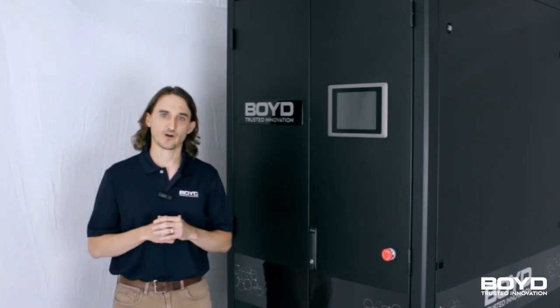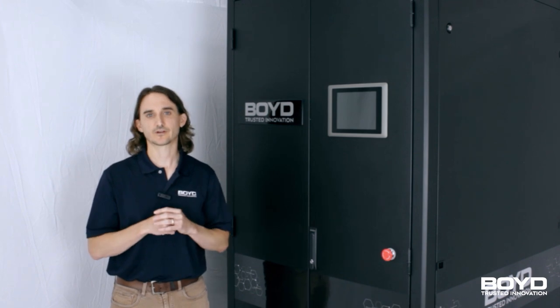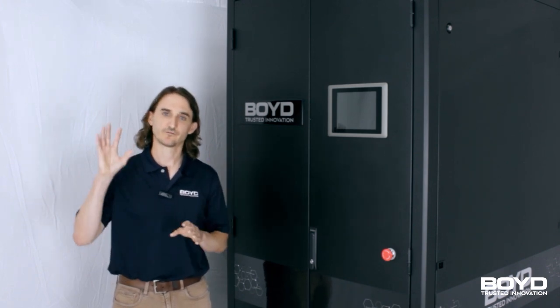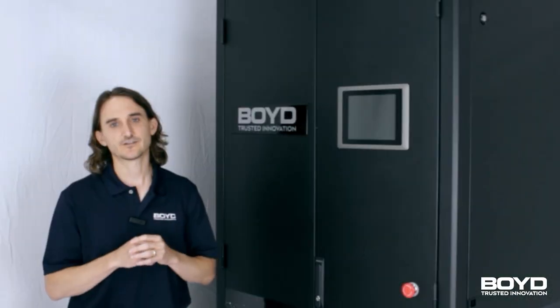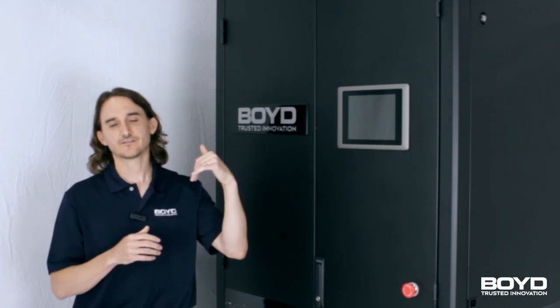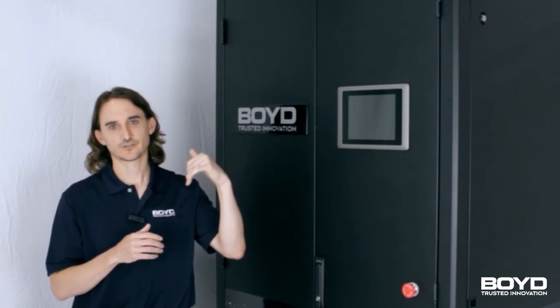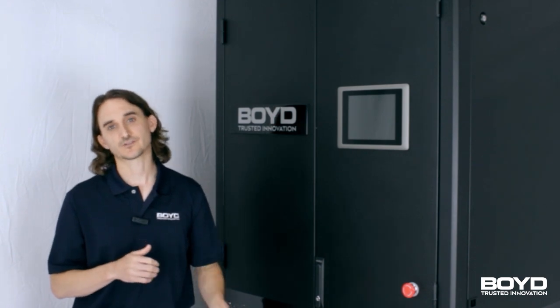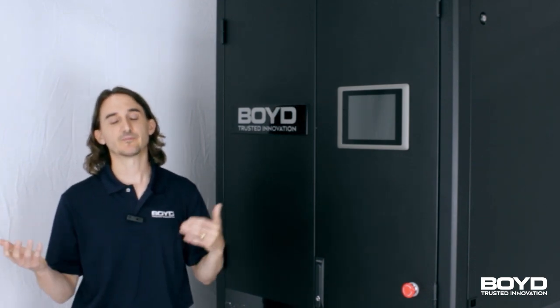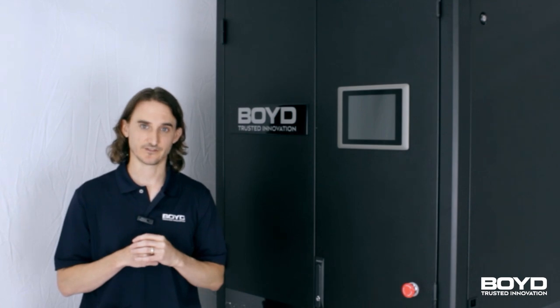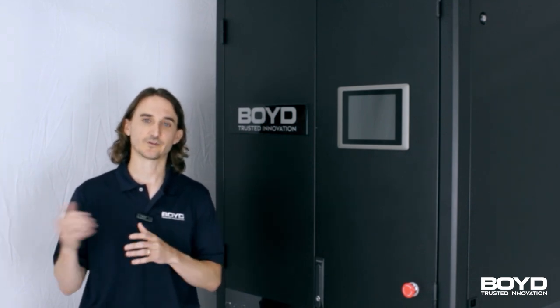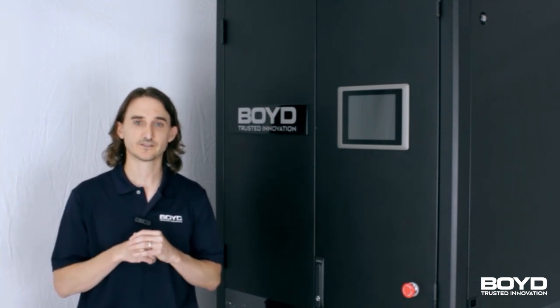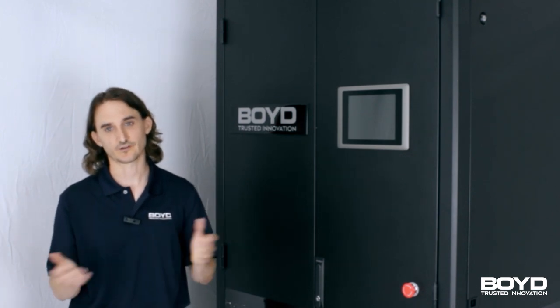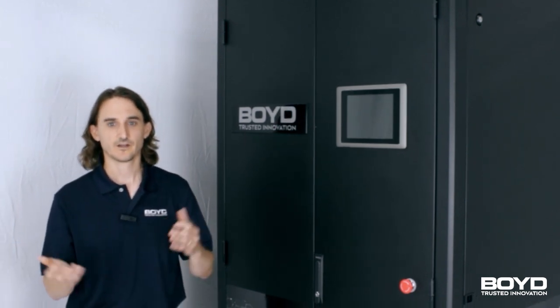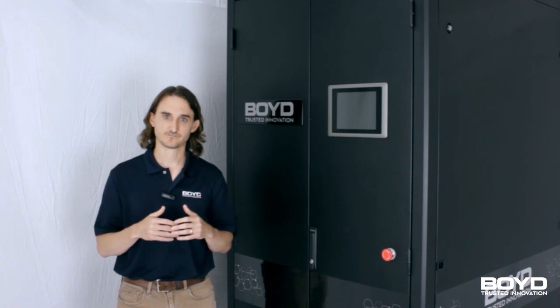Coming back to the electronics box, we have two primary enclosures to separate the high voltage from the controls. A single high voltage feed comes in to the electronics enclosure. We also have each pump on its own circuit breaker to enable them to be hot swappable if there is a failure. We also have redundant power supply on the 24-volt bus, which is how our controls and all of our sensors are operated. Coming back to the service of the system.